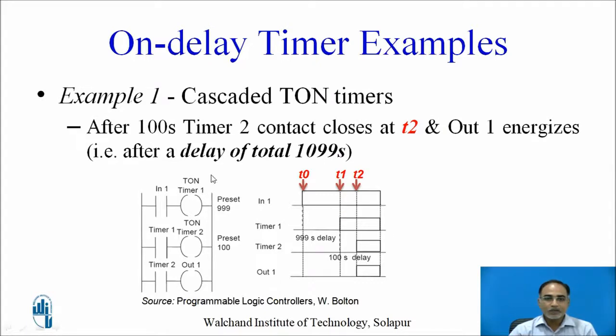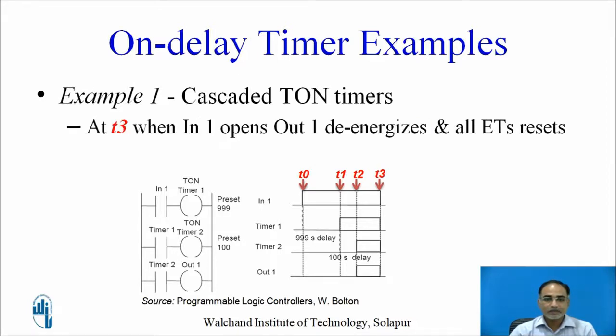After 999 seconds, timer 1 contact closes at t1 and timer 2 starts with PT equal to 100 seconds. At t2, after 100 seconds, timer 2 contact closes and output 1 energizes. The total delay inserted is 1099 seconds — with two cascaded on-delay timers you achieve a larger delay. At t3, when input 1 opens, output 1 and all ET values reset to 0.